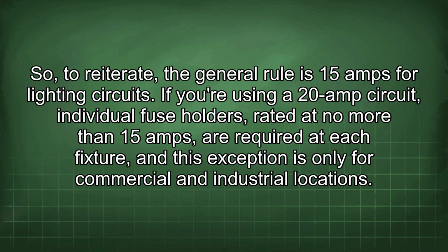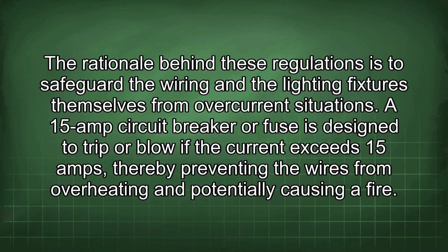So, to reiterate, the general rule is 15 amps for lighting circuits. If you're using a 20 amp circuit, individual fuse holders rated at no more than 15 amps are required at each fixture, and this exception is only for commercial and industrial locations. The rationale behind these regulations is to safeguard the wiring and the lighting fixtures themselves from overcurrent situations. A 15 amp circuit breaker or fuse is designed to trip or blow if the current exceeds 15 amps, thereby preventing the wires from overheating and potentially causing a fire.